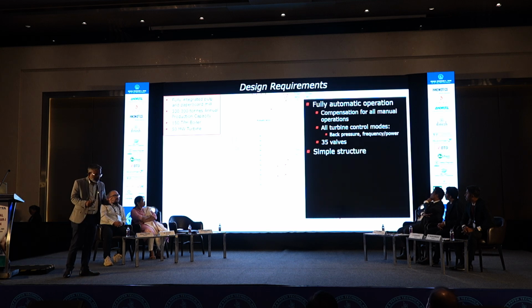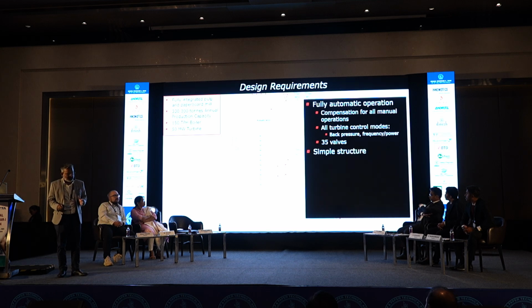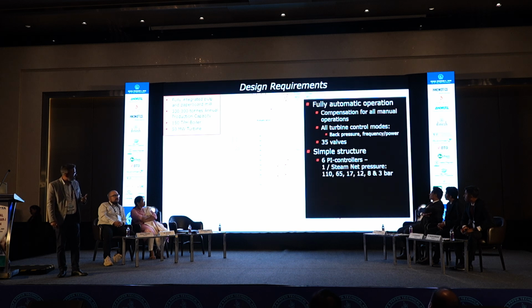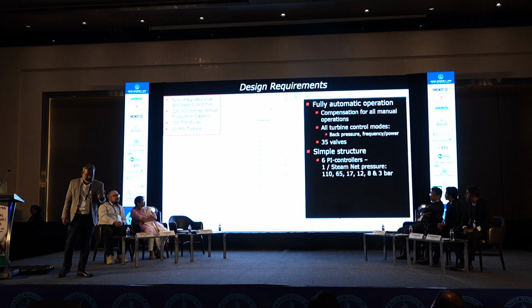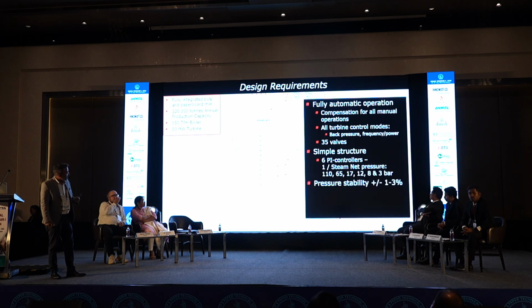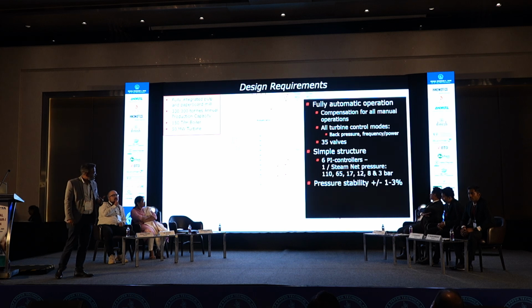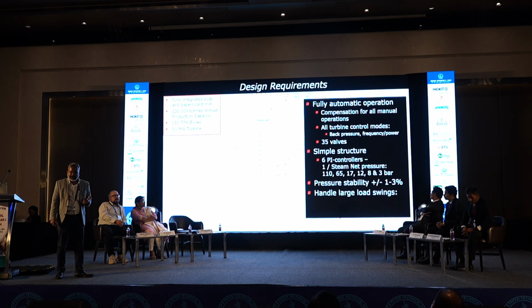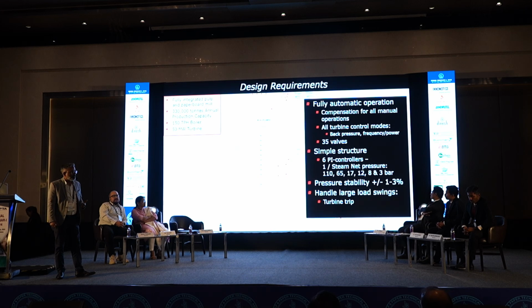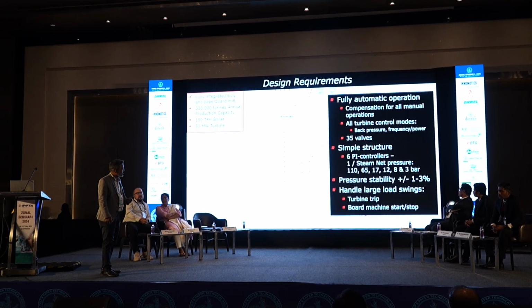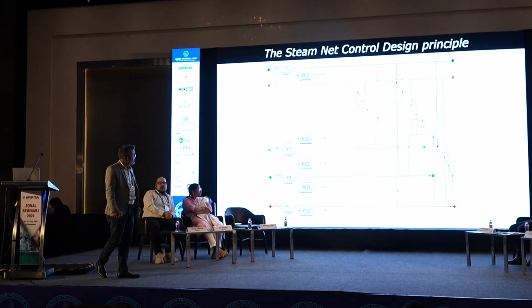So we developed a very simple control strategy for them. There were 6 steam headers, and for each steam header, we designed separate PI controllers. And we achieved pressure stability within 1 to 3%. And the system can handle large load swings like turbine trip or board machine start or stop.